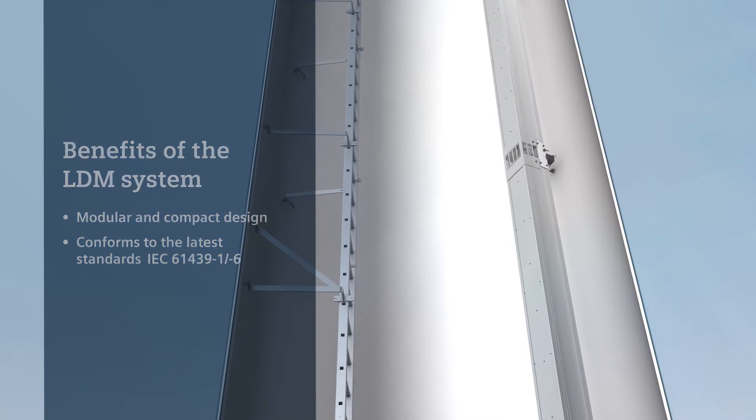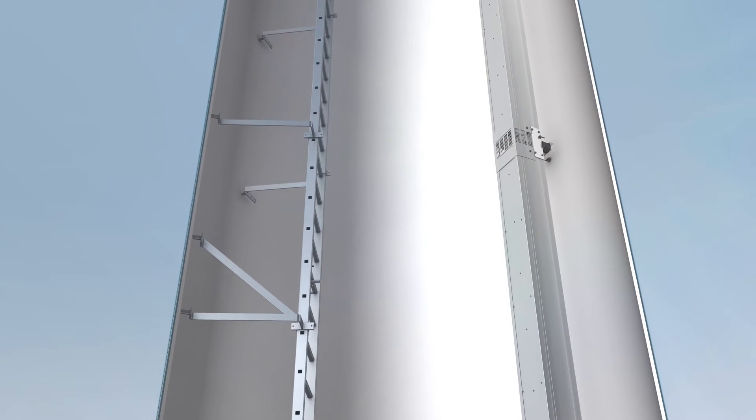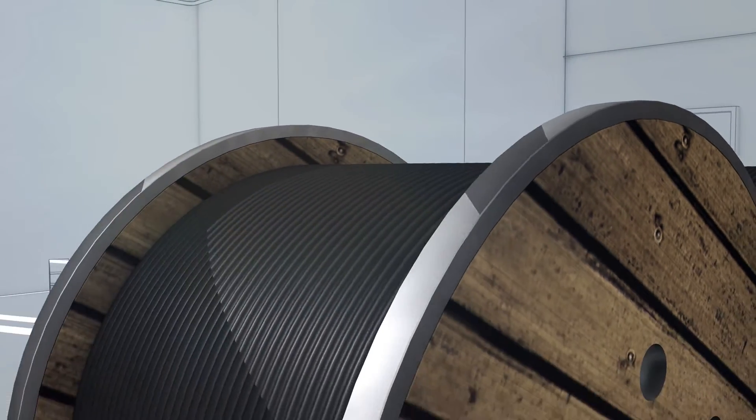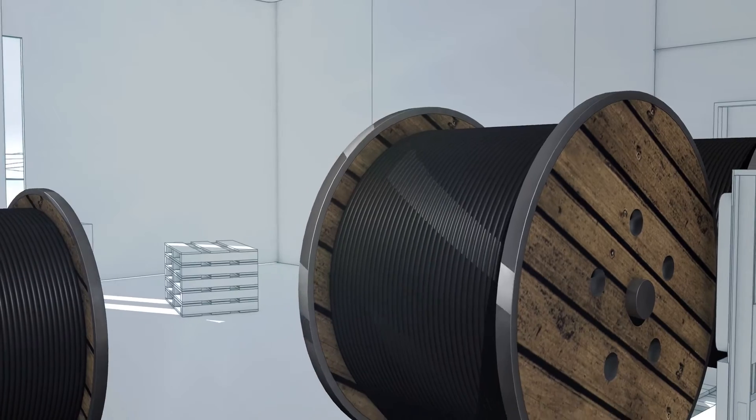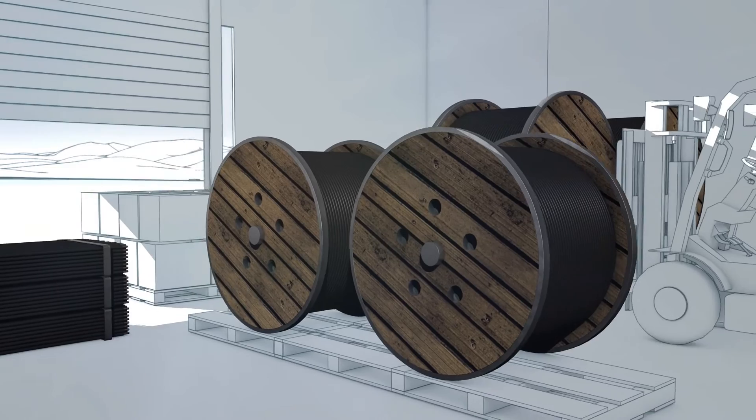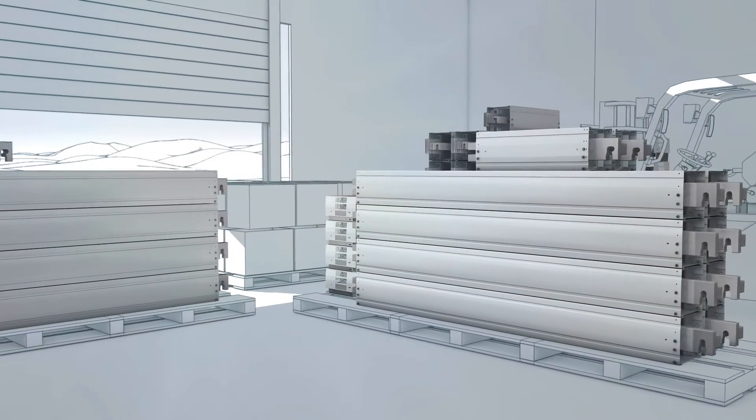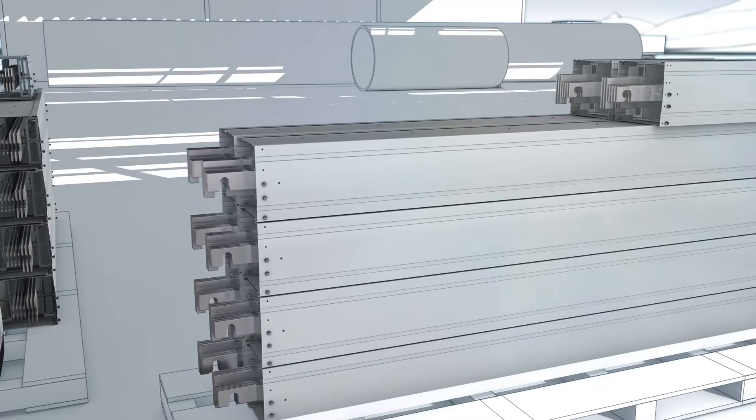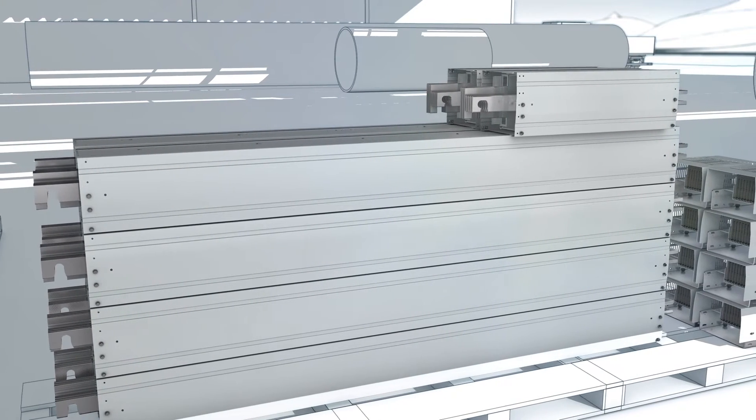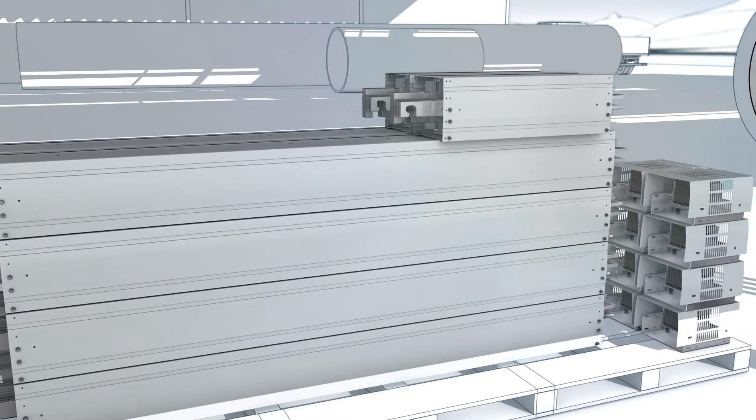The system conforms among other things to the latest standards IEC 61439 parts 1 and 6. Thanks to design verification by means of tests, it is exceptionally safe and reliable in operation. The benefits are already appreciable during the installation phase. In a cable based solution, the individual conductors must usually be cut to size through a complex process. With the LDM system however, a combination of several bus bar units is delivered precisely as a prefabricated assembly for each tower segment.